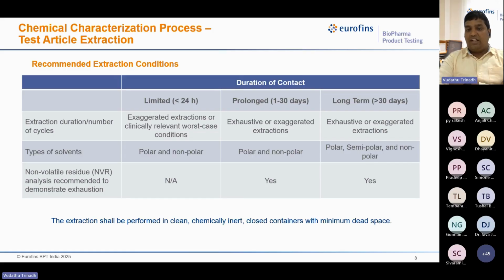Whereas if your medical device is prolonged and long-term, then out of exhaustive and exaggerated, there are some more conditions, in which case you have to select exhaustive and exaggerated. Whereas if your medical device is a single-use medical device, in contact for less than 24 hours, or if multiple single-use devices are used over several days during your medication, then exaggerated conditions are sufficient rather than exhaustive conditions. And if your medical device is reusable, that also you can consider as exhaustive considerations for extractions.